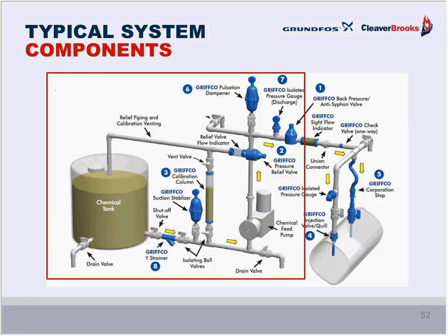This is the back pressure valve, or sometimes called a pressure loading valve, used in instances where the process pressure is lower than desired for pumps to dose accurately. Now, the pumps that use valves with check valves typically require 25 psi to seat the check valve. We need the manufacturer for guidance on how to set the back pressure valve to avoid either an overpressure or underpressure situation. In instances, process pressure will fluctuate, so it is not a reliable method to use process pressure or pressure losses in piping to seat the check valve, due to the varying velocities and pressures that we see in these systems.